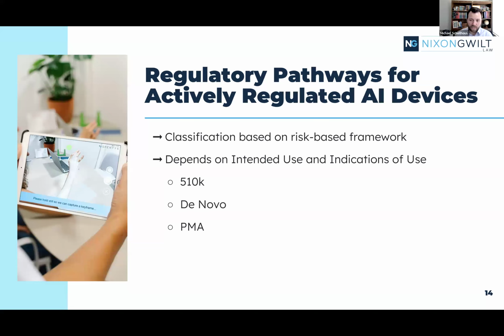The FDA is also likely going to require additional types of data validation and data submission to the FDA in order to demonstrate that. One of the questions we often see is, if a device has to come under a 510(k), is the FDA going to require clinical data or not? We do know that they're going to require non-clinical data like software validation, human factors testing, cybersecurity testing and validation, and all of those. Are they going to require clinical data?